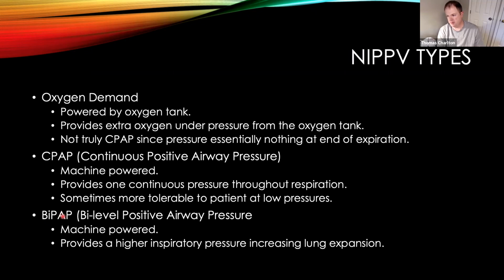BiPAP is bi-level positive airway pressure. This again is machine powered and provides a higher inspiratory pressure. The idea behind that is we want to try and get the lungs expanded as much as we can with as little work as possible. So the machine can actually sense when somebody begins to take a deep breath, and will spool up the pressure. That motor will kick up and provide additional pressure. One of the common settings that we'll use is 12/8.